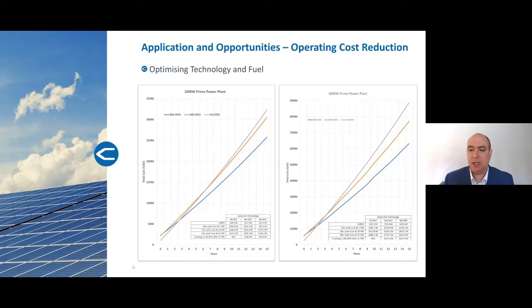The medium-speed units use less fuel and have longer maintenance intervals, but are more expensive in upfront capex than their high-speed counterparts. The study looked at two scenarios: a prime power plant of 10 megawatts and one of 30 megawatts in size.